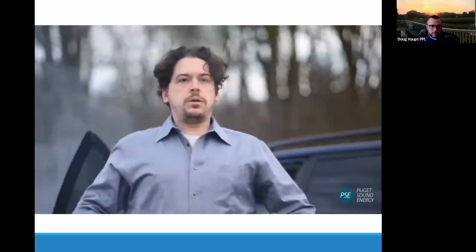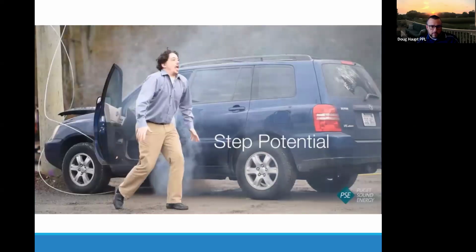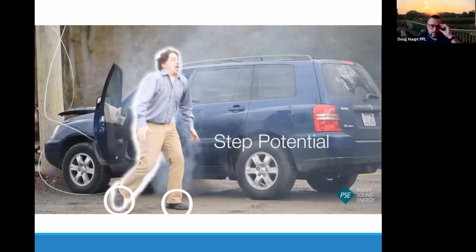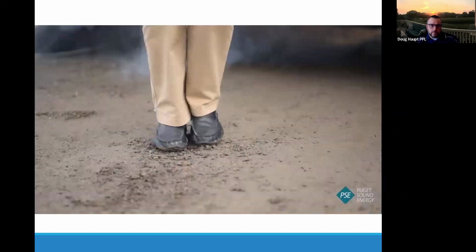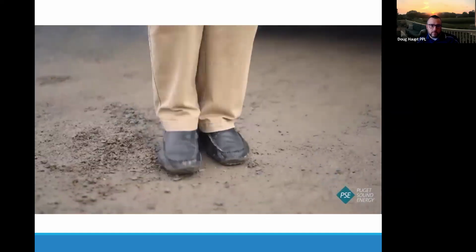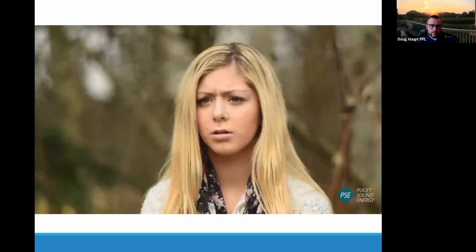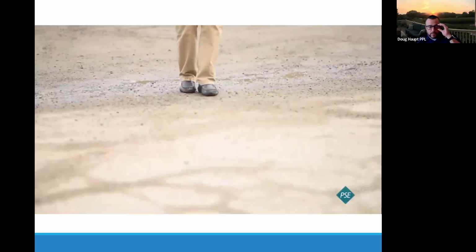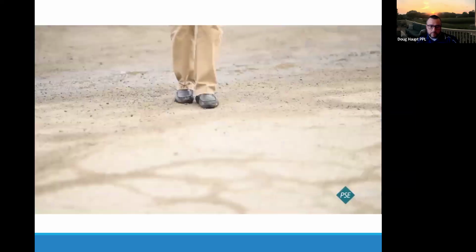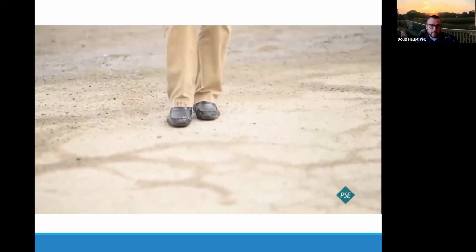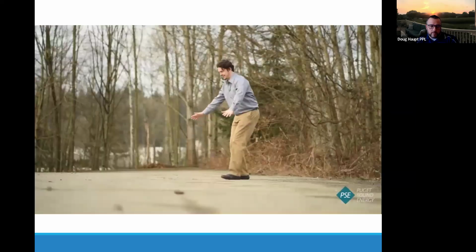Now, step potential: because the ground is energized, electrical current can travel through me if my feet aren't close together. Electrical current enters through one foot and out the other. The further apart my feet are, the greater my chances of getting shocked. So I must move away using short, shuffling steps. Shuffle, shuffle, shuffle, there you go. You got this, Stephen, no large steps. Just keep on shuffling, every day I'm shuffling.